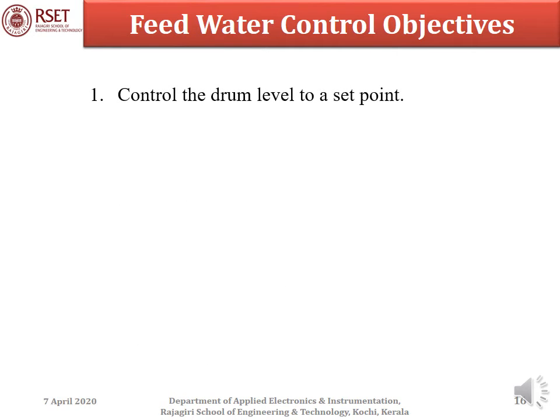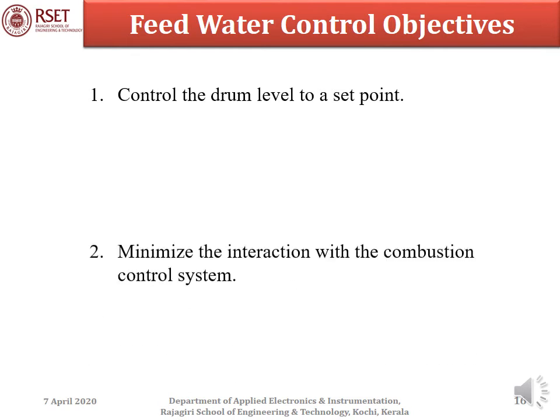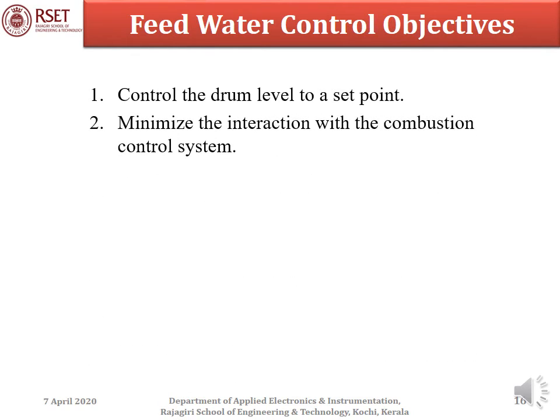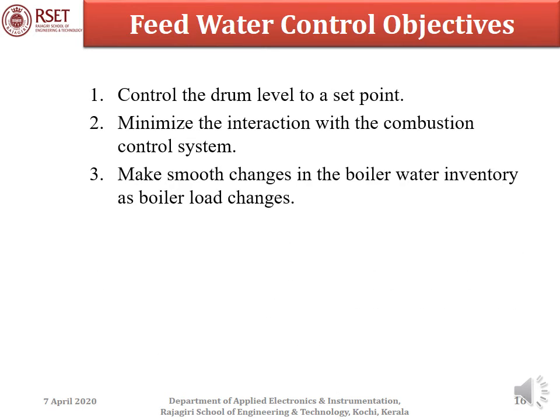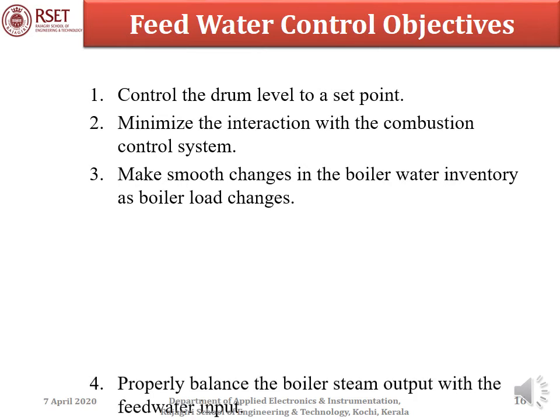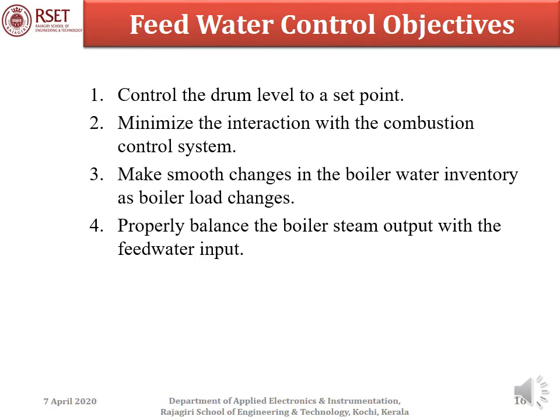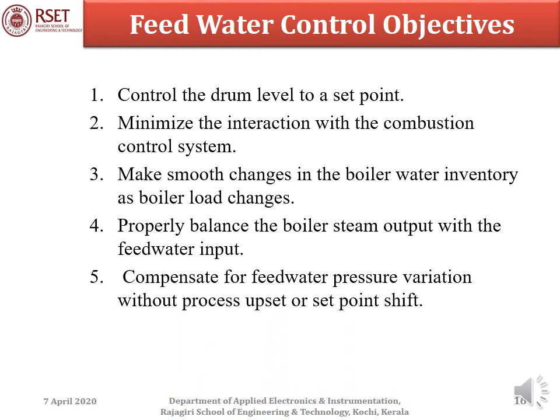The control objectives are: control the drum level to a set point; minimize the interaction with the combustion control system; make smooth changes in boiler water inventory as boiler load changes; properly balance the boiler steam output with the feed water input; and compensate for feed water pressure variation without process upset or set point shift.